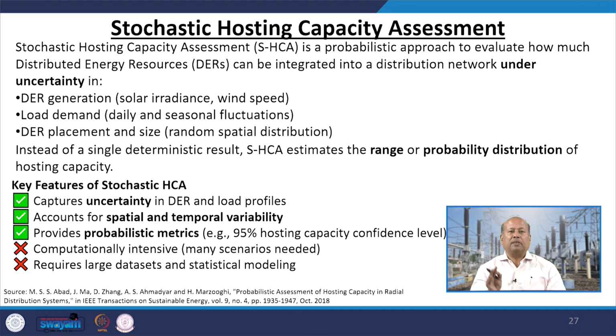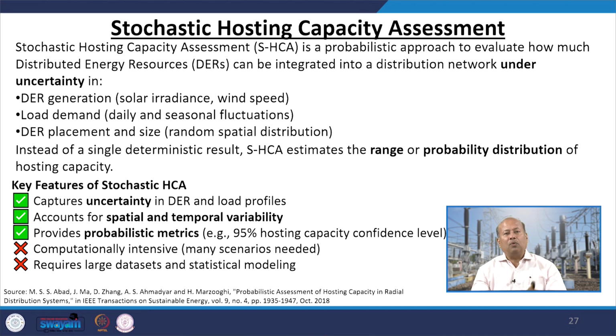Instead of a single deterministic result, SHCA estimates the range or the probability distribution of the hosting capacity. Instead of saying very specifically that 2 megawatt at bus number 18 is acceptable, it can give you an overall range or a probability distribution characterizing how this hosting capacity must look. So, what are the key features of stochastic HCA? It captures uncertainty in DER and load profiles, accounts for spatial and temporal variability, and provides probabilistic metrics, whereas computationally it is very intensive and complicated, and requires large data sets and statistical modelling.